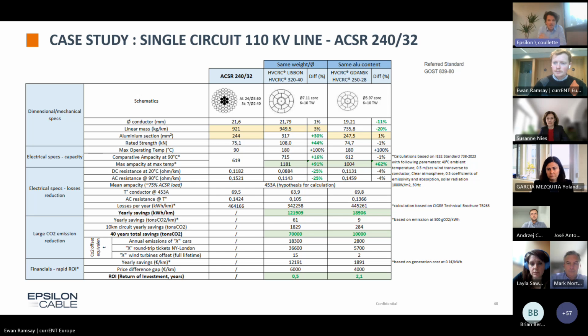So what we can see is that if we combine those benefits, either the higher aluminum content and also the ability to double the maximum operating temperature, the line losses can be reduced by up to 25%, considering the DC losses and AC losses, with a mean ampacity of about 450 amps, which corresponds to 75% of the ACSR load. So turned into savings, what does it mean?